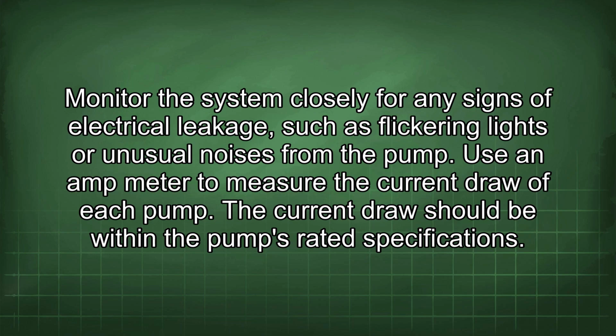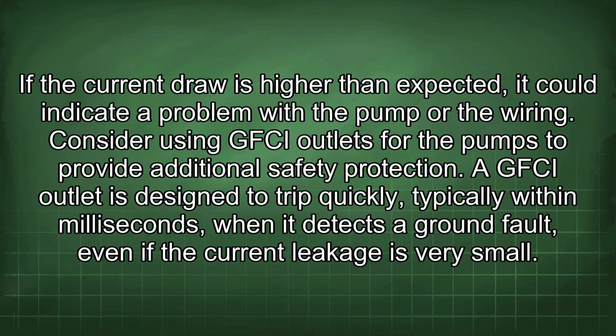Monitor the system closely for any signs of electrical leakage, such as flickering lights or unusual noises from the pump. Use an amp meter to measure the current draw of each pump. The current draw should be within the pump's rated specifications. If the current draw is higher than expected, it could indicate a problem with the pump or the wiring.